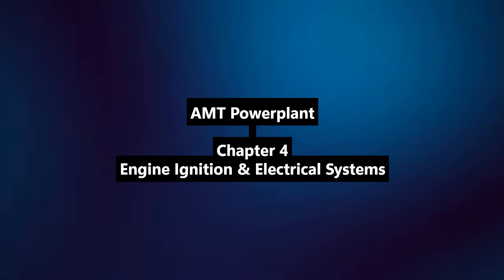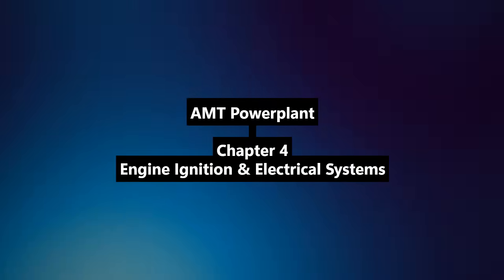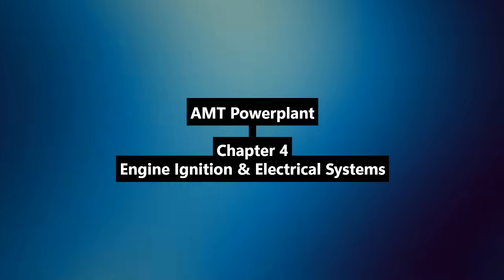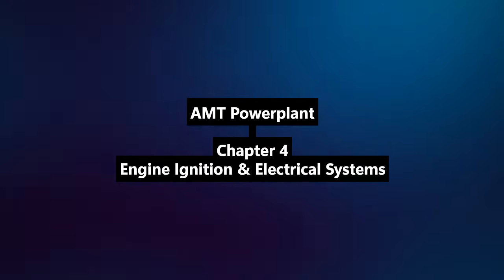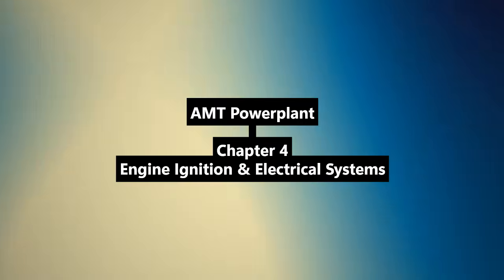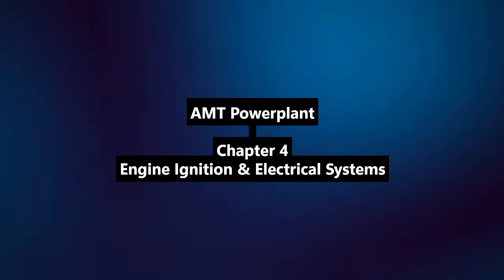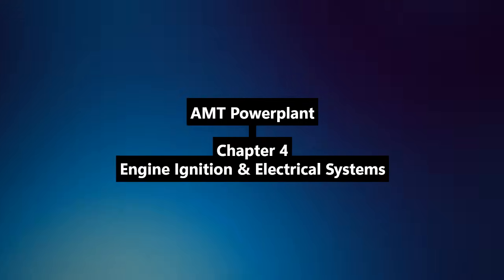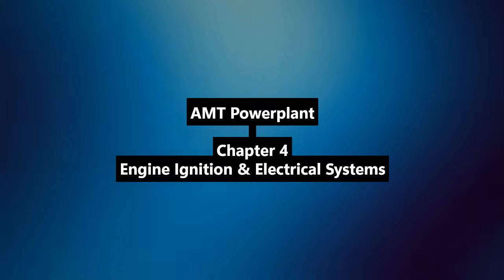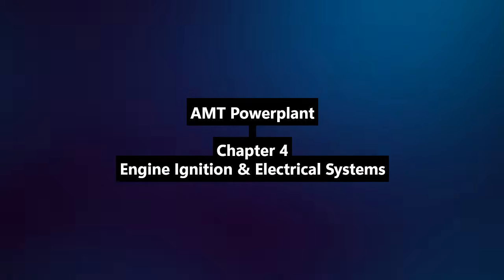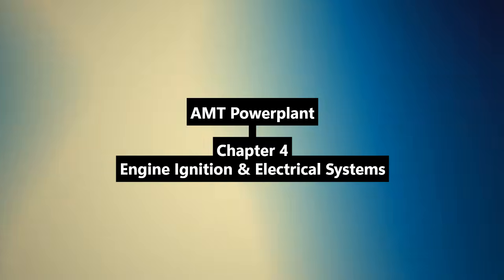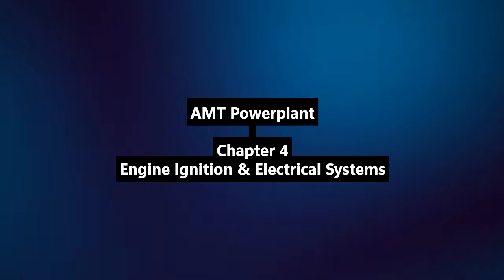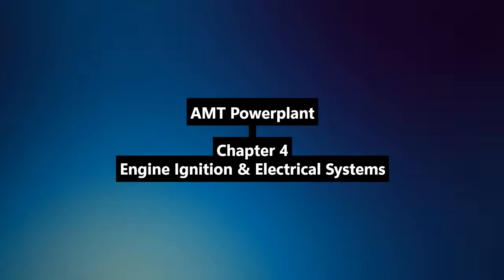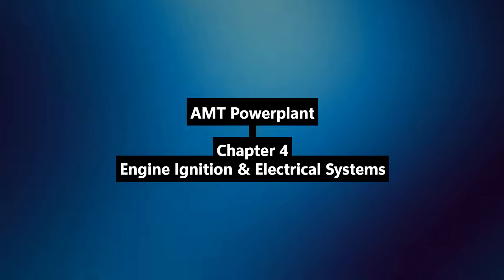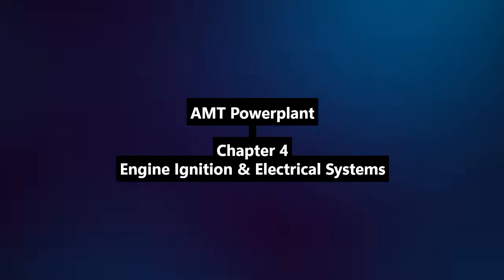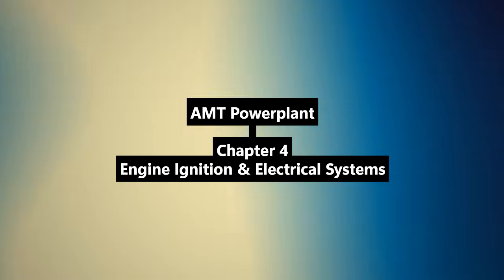And clean up afterwards. Absolutely critical. After seating, all traces of carbon dust must be meticulously cleaned out from inside the generator using compressed air or a soft brush. And a big warning: never use emery cloth or any abrasive material containing metallic particles. Why not emery cloth? Because the conductive particles can embed in the soft carbon brushes and the copper commutator bars, leading to shorting between segments, arcing, and serious damage. Only use fine sandpaper. Got it.